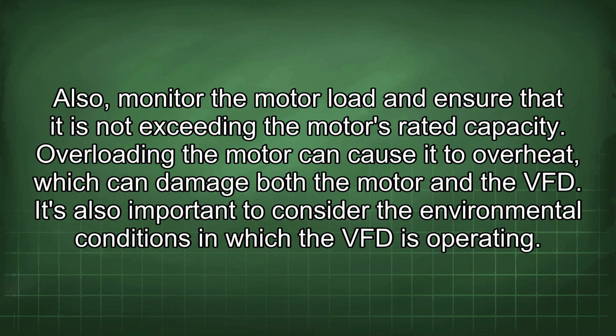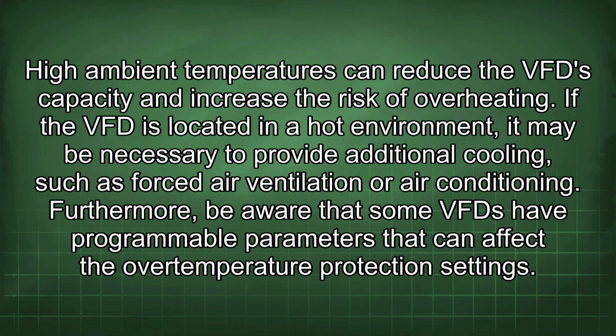It's also important to consider the environmental conditions in which the VFD is operating. High ambient temperatures can reduce the VFD capacity and increase the risk of overheating. If the VFD is located in a hot environment, it may be necessary to provide additional cooling, such as forced air ventilation or air conditioning.